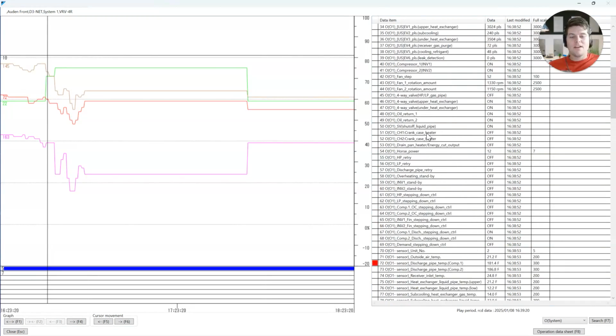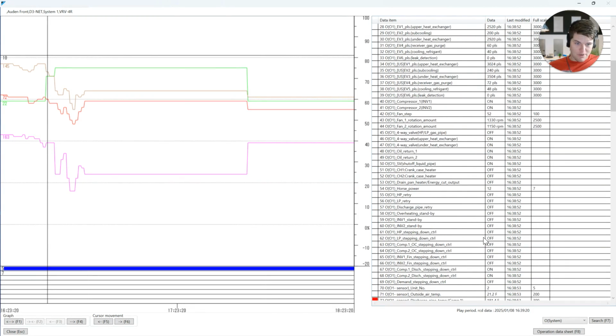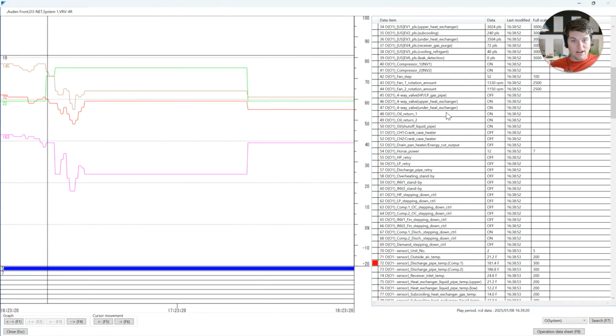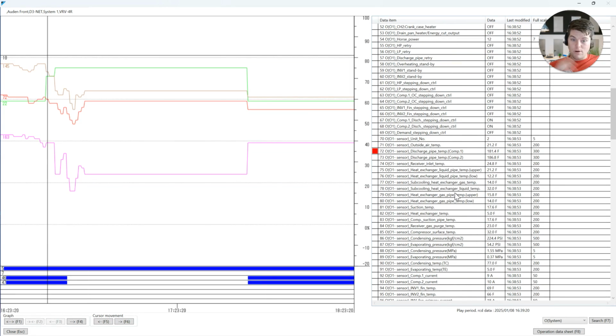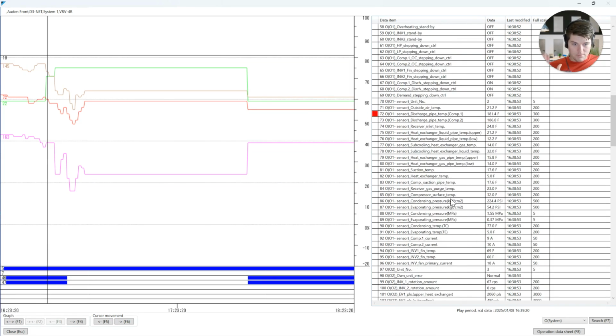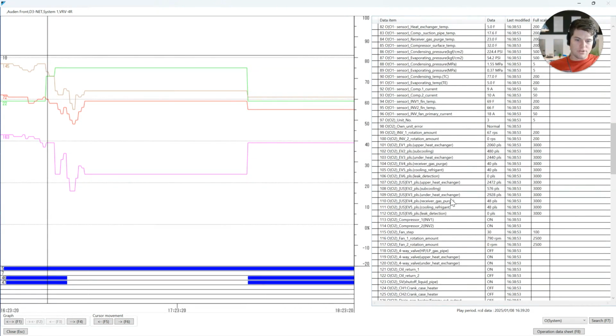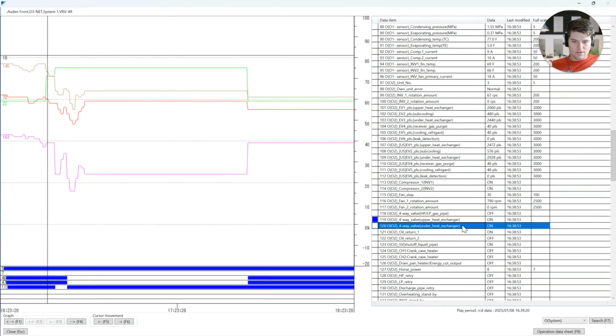Ready? Okay. So we know we're going into defrost. It's prepping for defrost. Now what I need to do is add my 4-way valves. Not my dual gas because I'm not worried about that. We're not switching modes, so that doesn't matter to me. Filter out the information that matters and add what only we need to see.